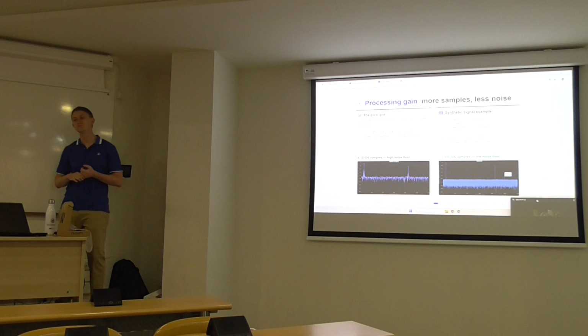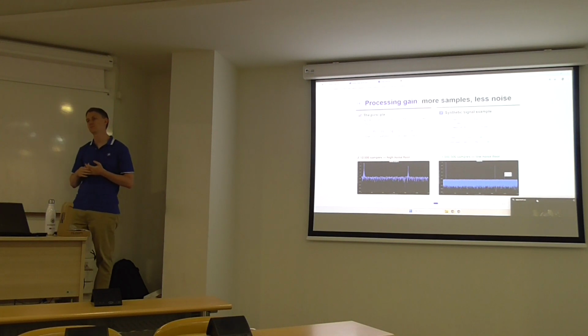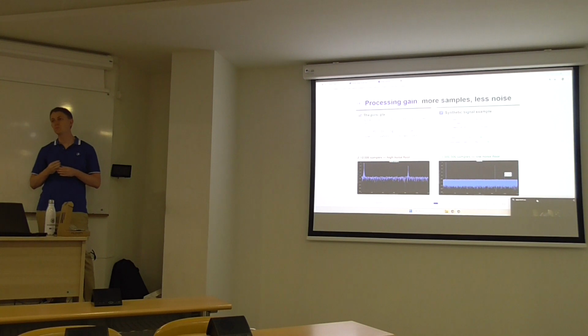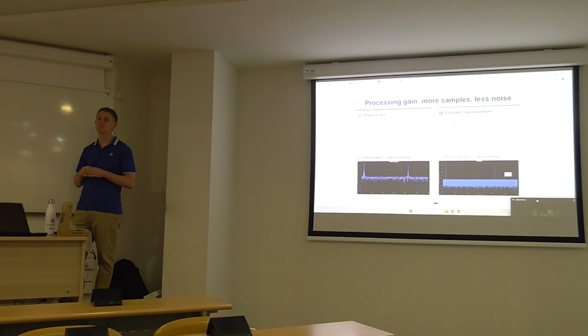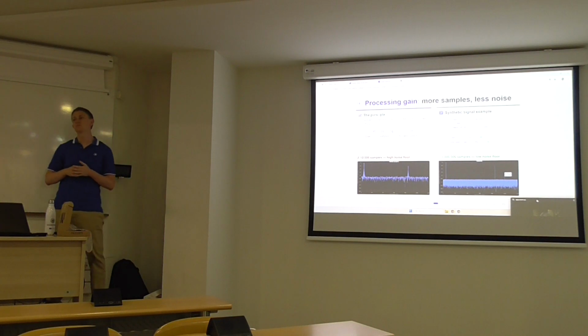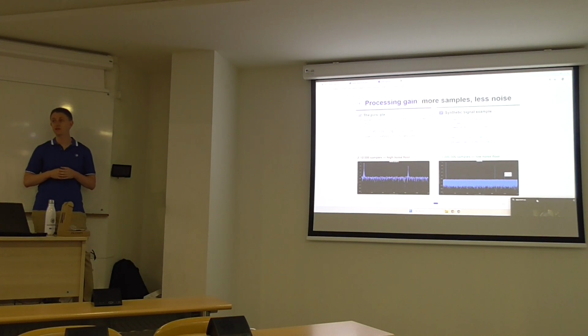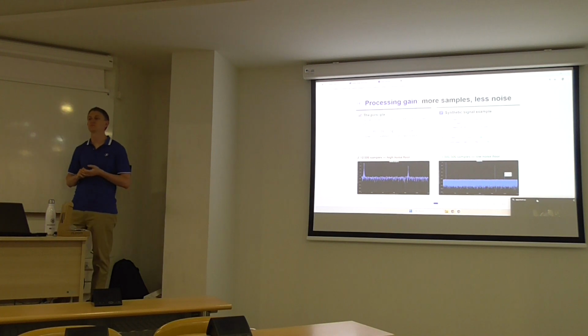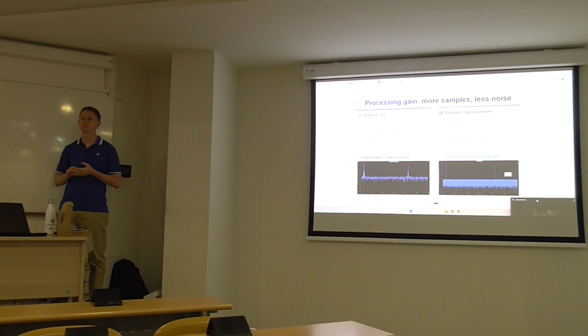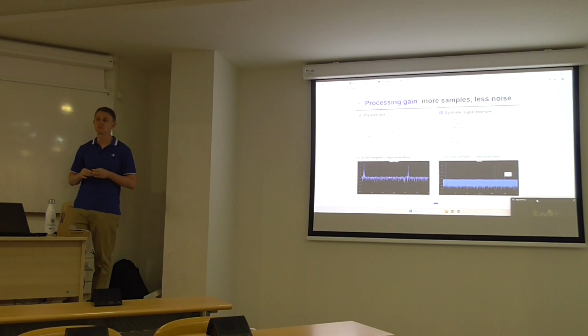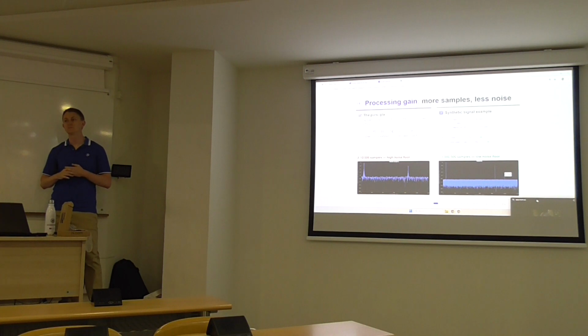The other one is just an addition to what you said, and maybe you want to adopt that when you give the same lecture again. The RSH naturally exist in the machine because they are a design characteristic of the machine. They are there because they express the main magnetic field of the rotor, and so they take into account the phases of the rotor, which is the number of the bars, correct? The opposite is true for eccentric machines. And that's why the amplitude is so much higher than the noise floor, because they are supposed to be there.